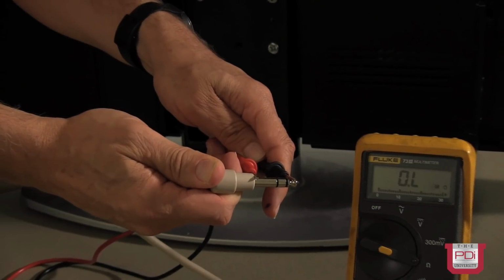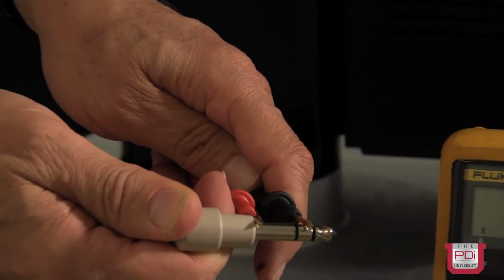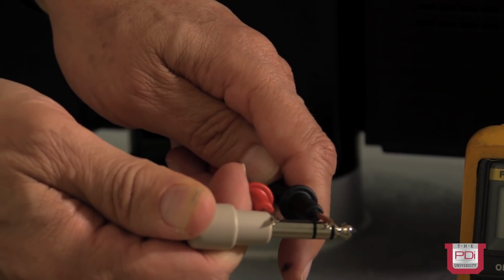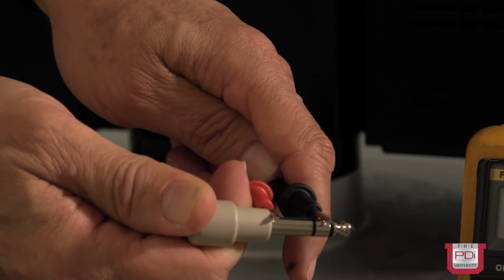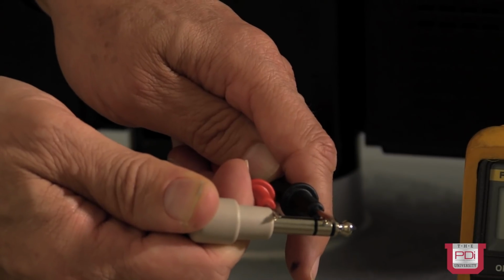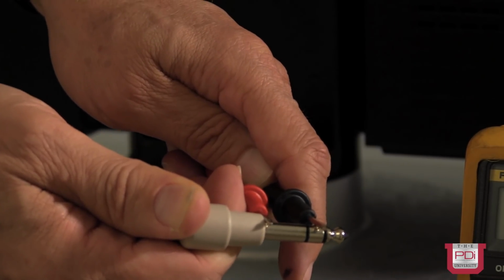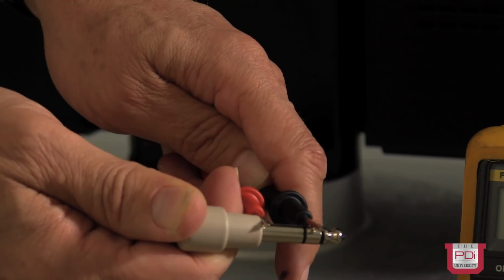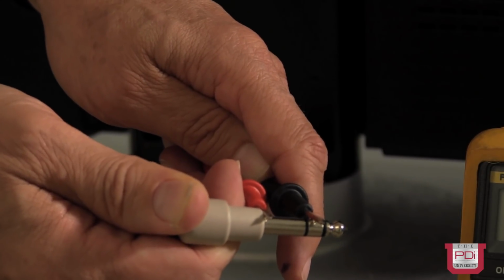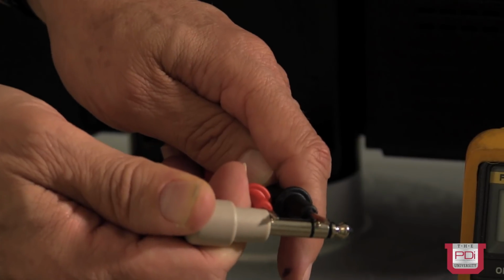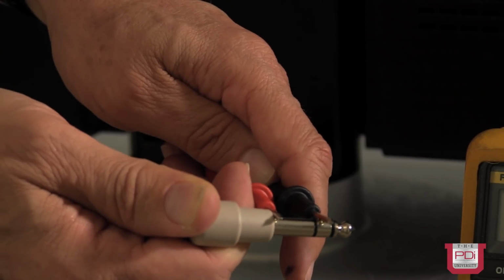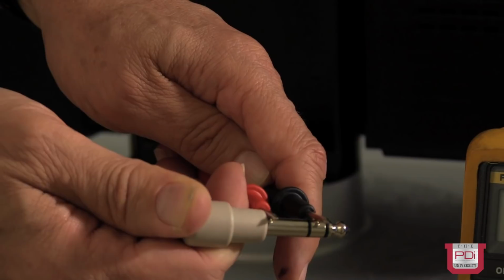The next circuit to check would be the control or data circuit, and that would be measuring between the common and the center band or the ring. And a correct reading would be an open circuit or very, very high resistance in mega ohms. If you see anything like a short or low, very low resistance in the kilo ohms, that may be an indication that you have a wiring fault and something has to be checked.